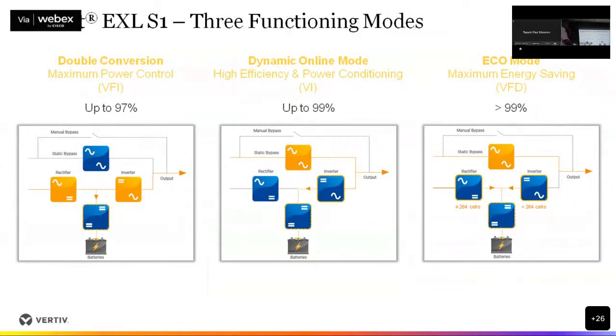And one more advantage: component utilization is very, very low, because most of the time your static bypass is on and the inverter acts just as a harmonic filter, with the rectifier kept on. So most of the switching devices are not actively on, only coming up partially, and the reliability of the whole product goes up.